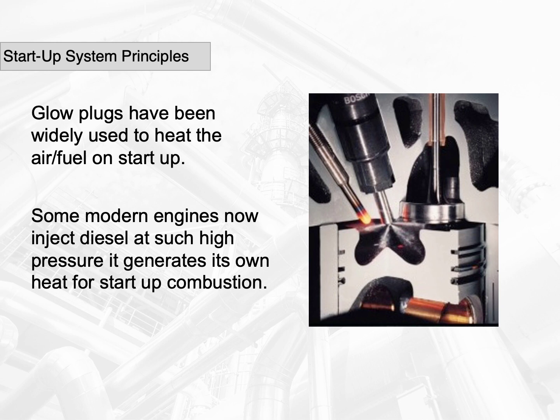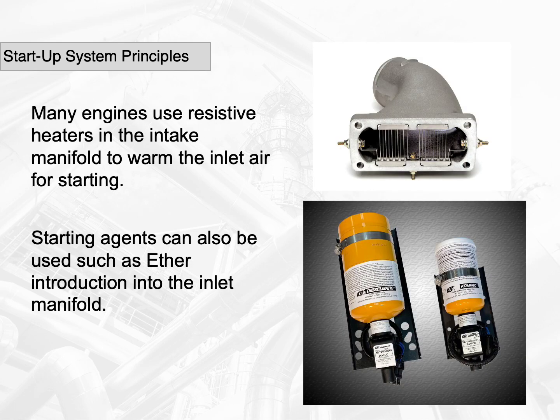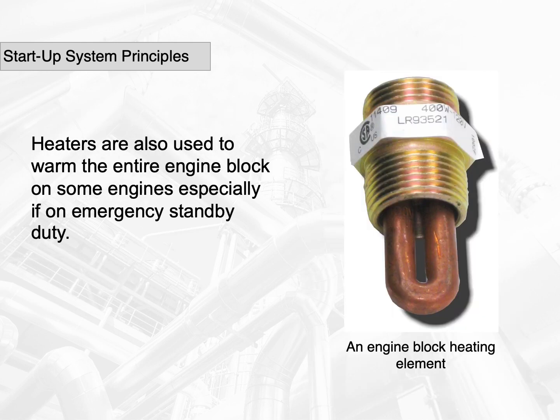Glow plugs have been widely used to heat the air/fuel on startup. Some modern engines now inject diesel at such high pressure, it generates its own heat for startup combustion. Many engines use resistive heaters in the intake manifold to warm the inlet air for starting. Starting agents can also be used, such as ether introduction into the inlet manifold. Heaters are also used to warm the entire engine block on some engines, especially if on emergency standby duty.